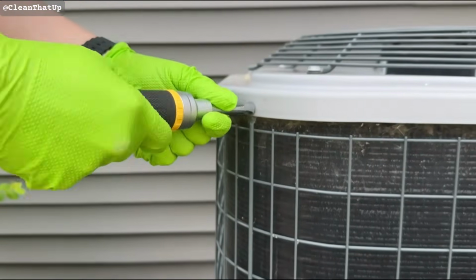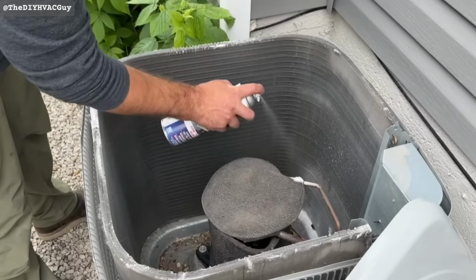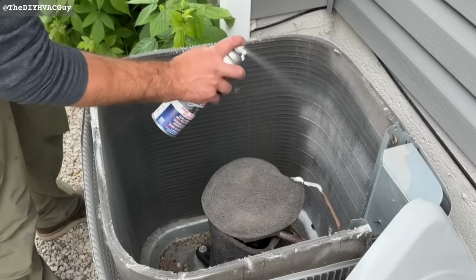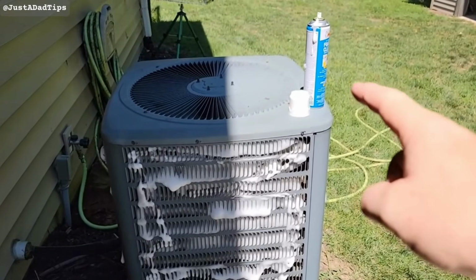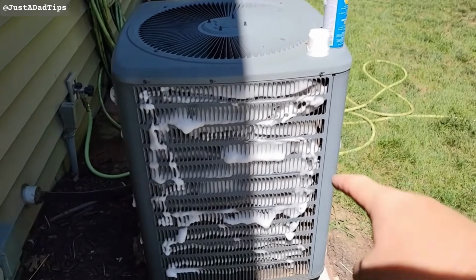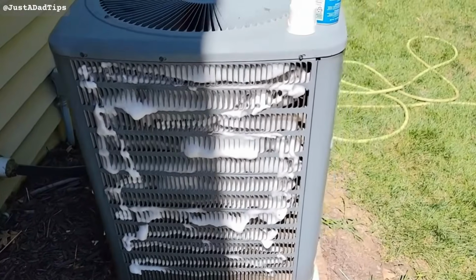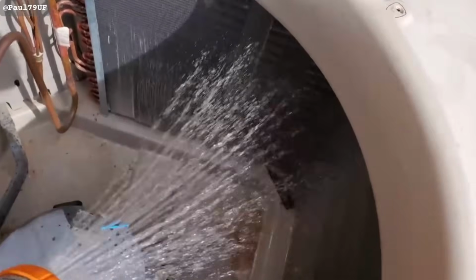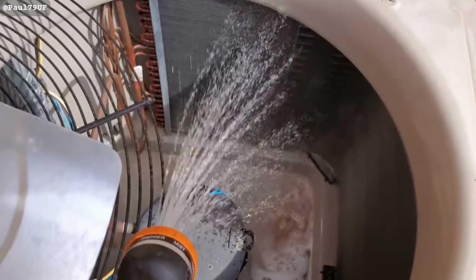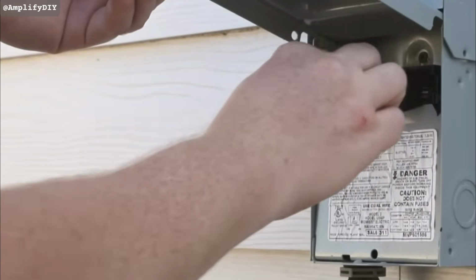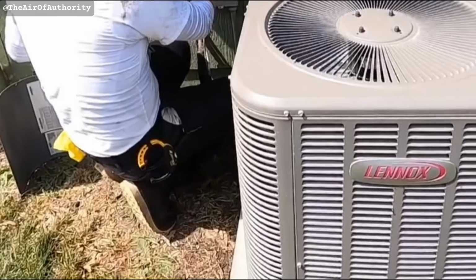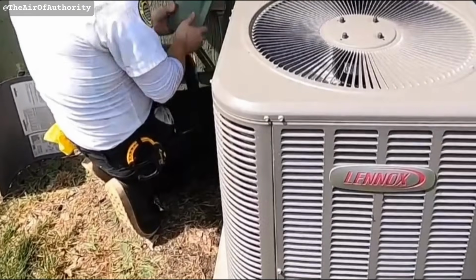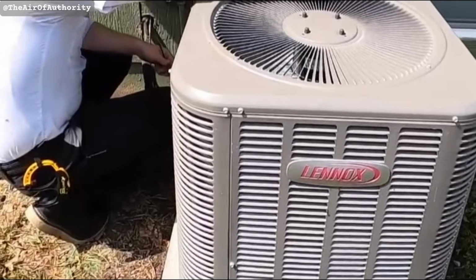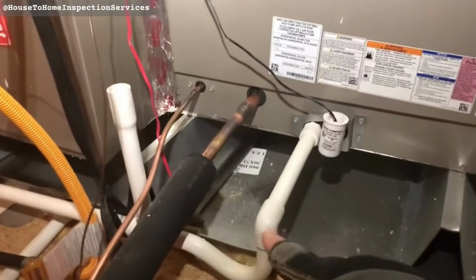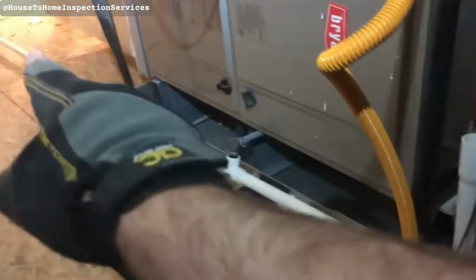The procedure is simple. Run the system in cooling mode for 15 minutes. Actually, in 100-degree weather, make it 20, so the readings stabilize. With a $15 infrared thermometer, take the temperature at a return air grill away from any supply registers. Then take the temperature at a supply register, ideally one of the central registers, not the farthest one from the air handler. Subtract supply from return. That's your temperature split. 16 to 22 degrees, the system is healthy.